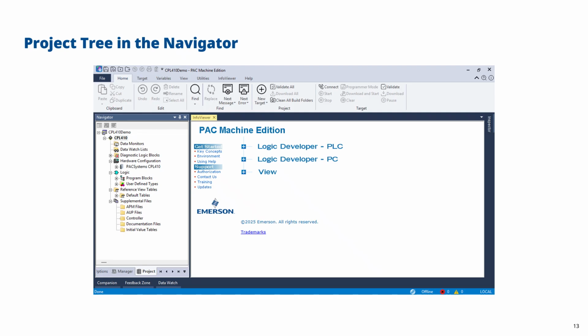The idea is that when you create variables, you can give them initial values. If you make changes to the controller and update those initial values, you can upload those initial value tables so that when you download, those initial values are part of the project. That's very good for recovery after maybe the failure of a PLC, or if you're storing multiple projects across multiple PLCs, you can have those initial values as part of your application logic rather than entering all of them manually.